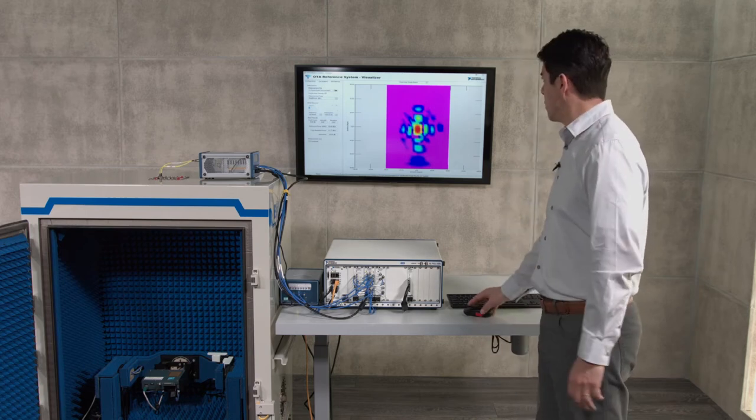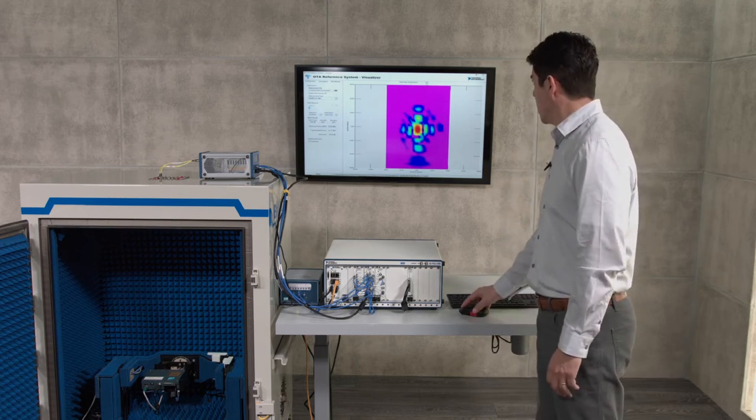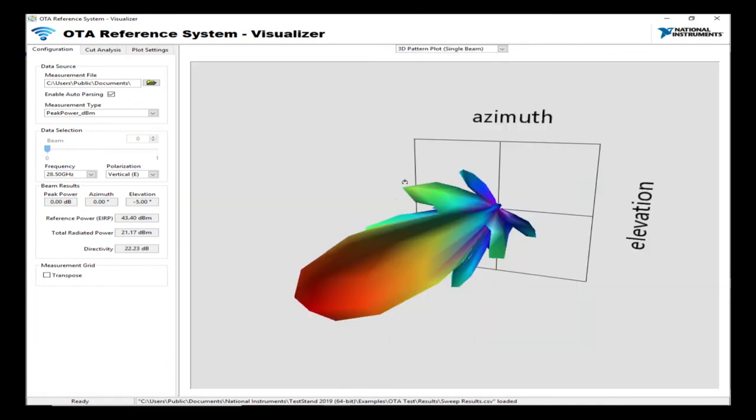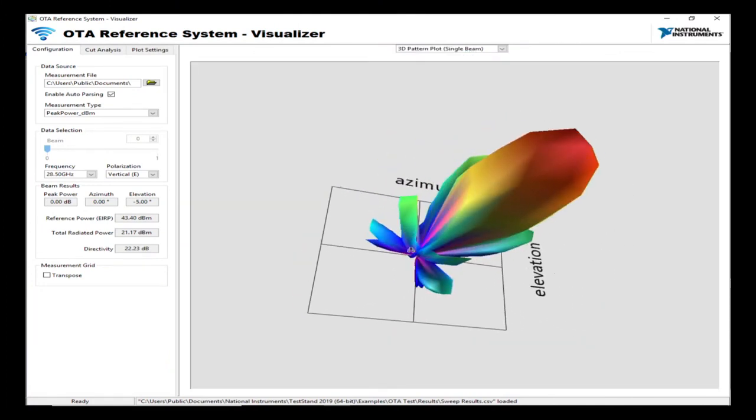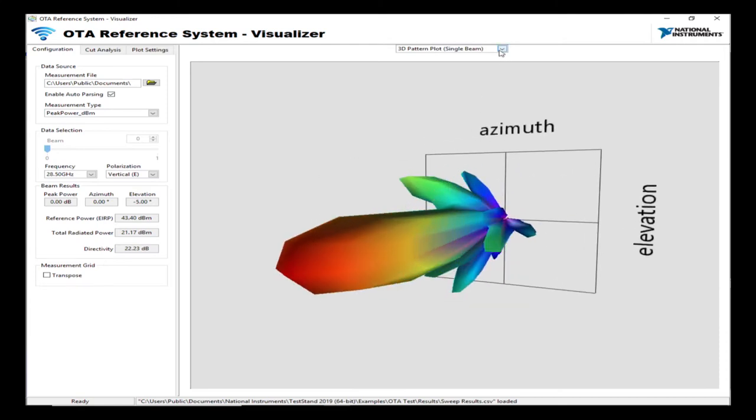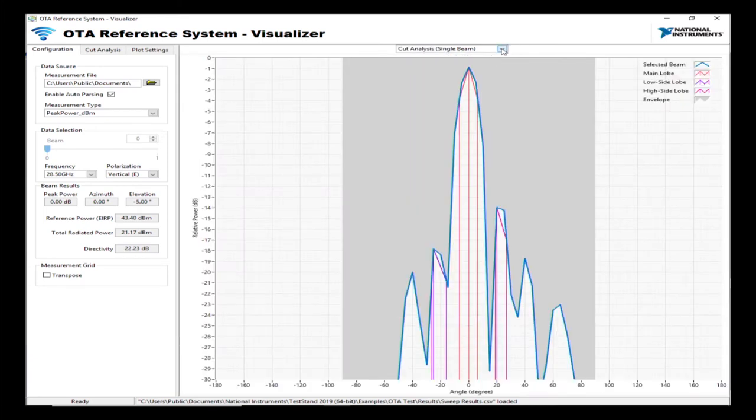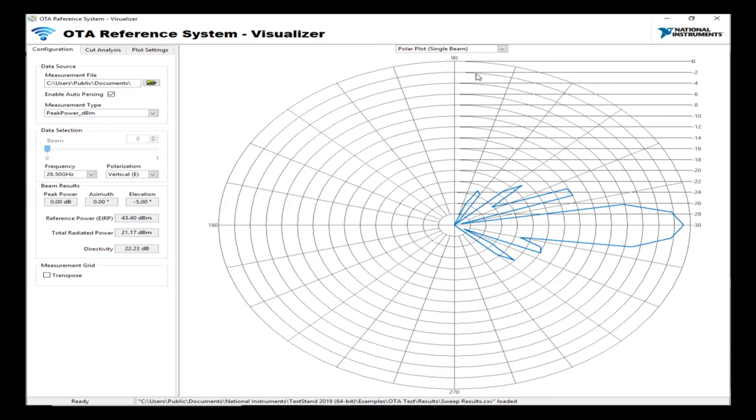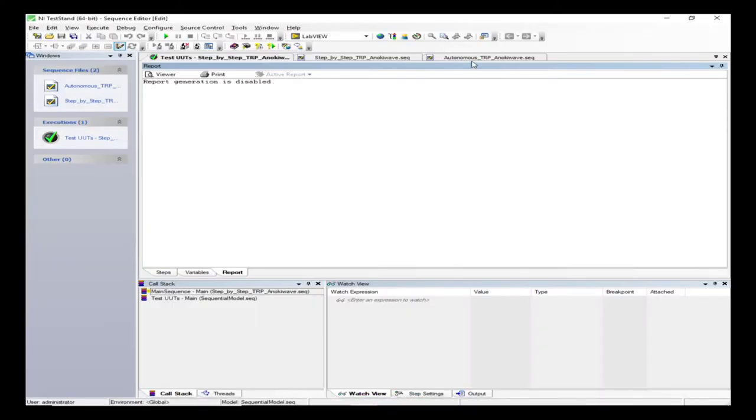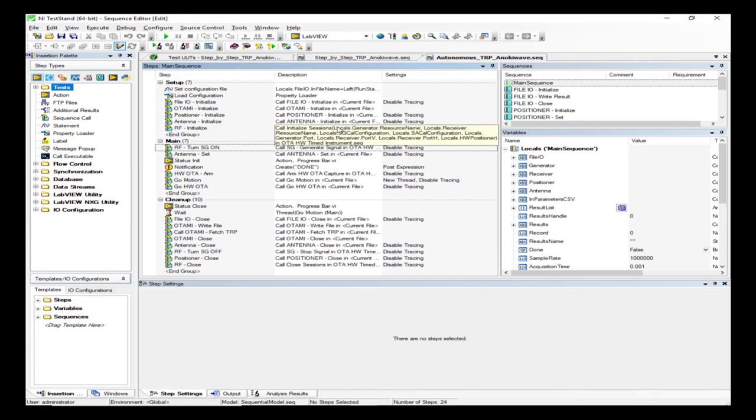And we can see here some of those visualizations, like the flat heat map. We can look at the 3D pattern plot and look at the characteristics of the beam, or look at the H and V cut analysis or even polar plots. Now let me switch over to a faster way of running these tests.